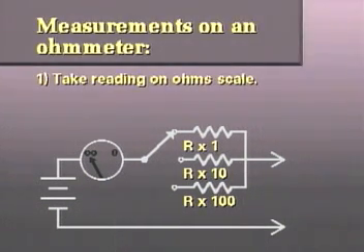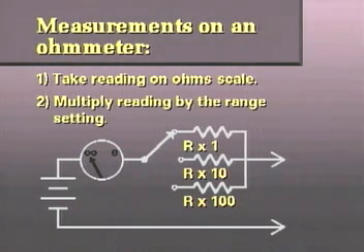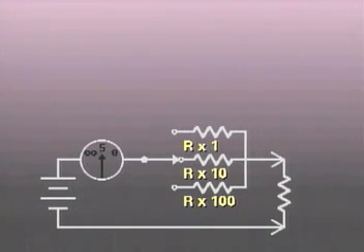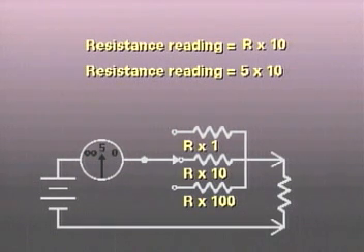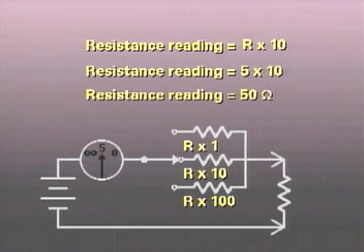Measurements are taken by first noting the reading indicated by the pointer on the ohm scale. The number is then multiplied by the range setting. For example, if this ohmmeter is set to r times 10, and it measures a resistance of 5 on the meter scale, that 5 needs to be multiplied by 10. The resistance we have measured, therefore, equals 50 ohms.